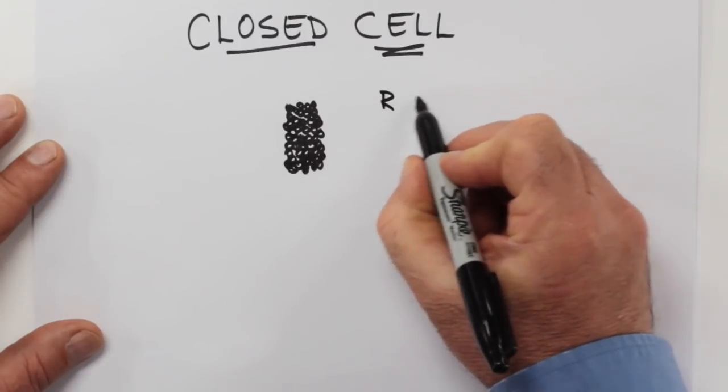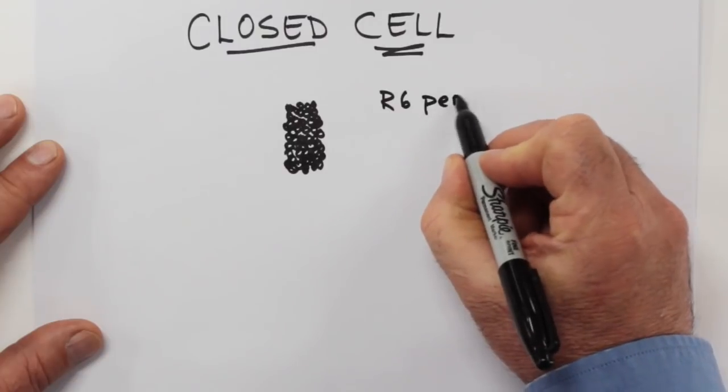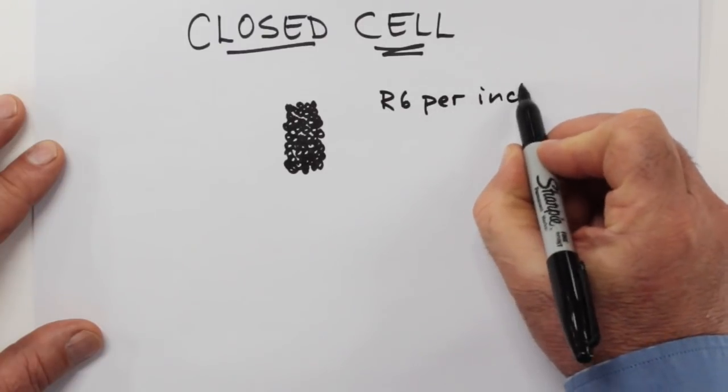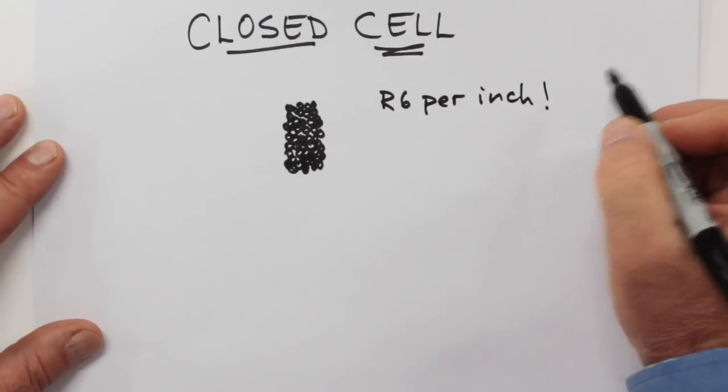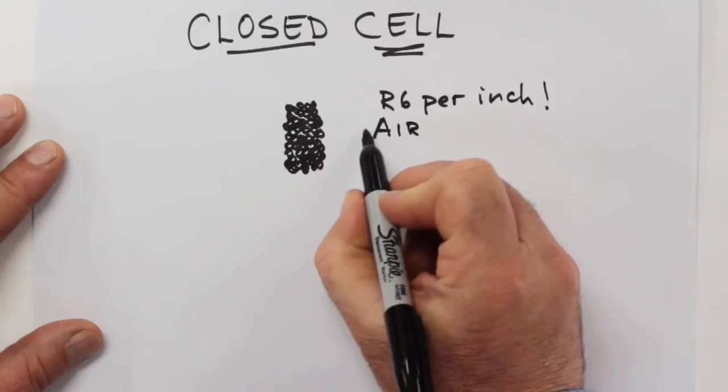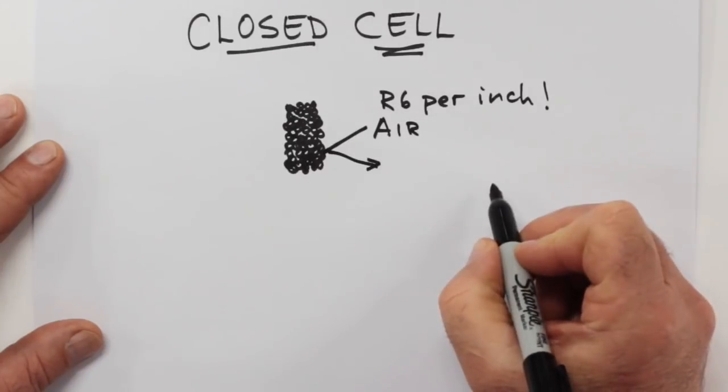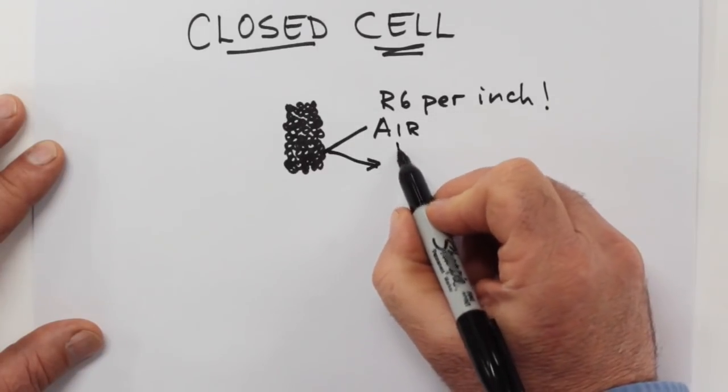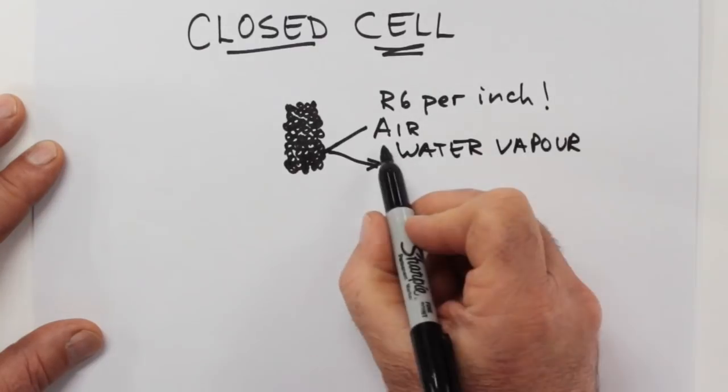Besides the fact that closed cell foam delivers on average a whopping R6 per inch and the fact that it can block air movement completely, so drafts and air leakage of all kinds, the ability to block water vapor is a hidden and really useful feature.